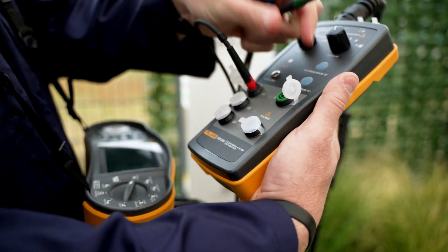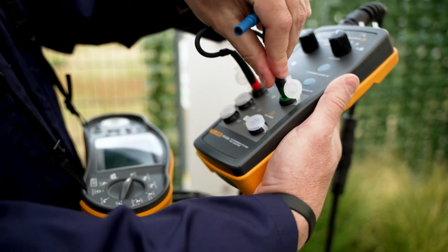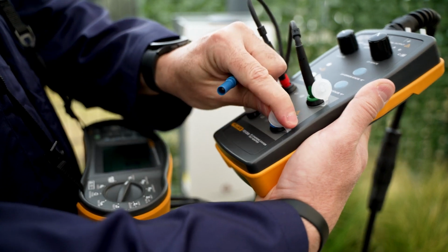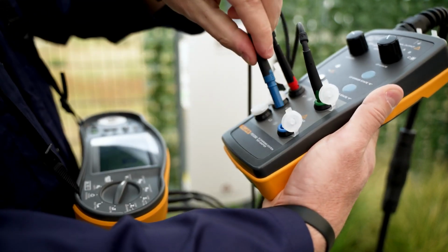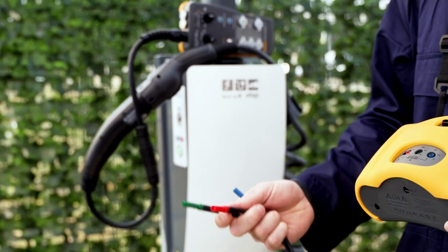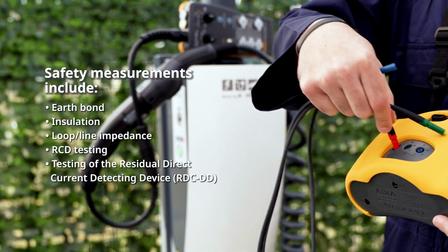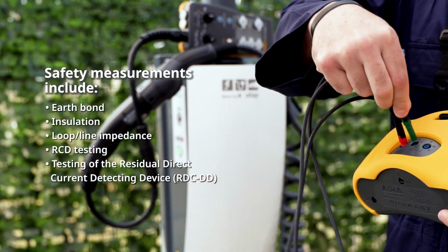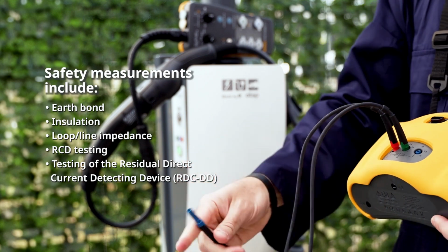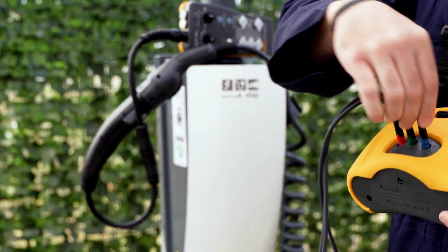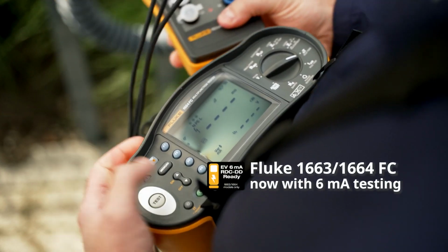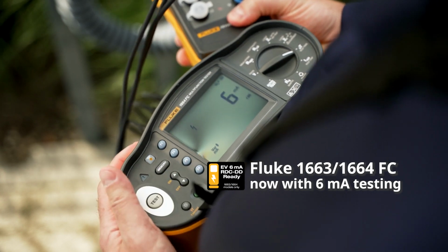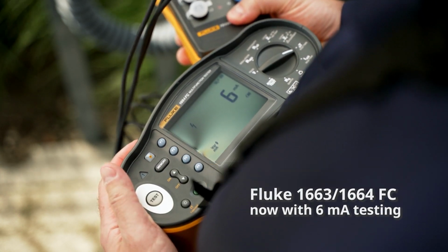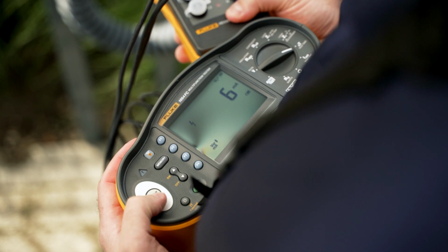Furthermore, the FEV300 is compatible with the 1663 and 1664 FC multifunction installation testers from Fluke, which allows for a variety of safety measurements. This integration facilitates quick and easy testing of RDC-DD, providing additional protection against 6 mA DC leakage currents on charging points.